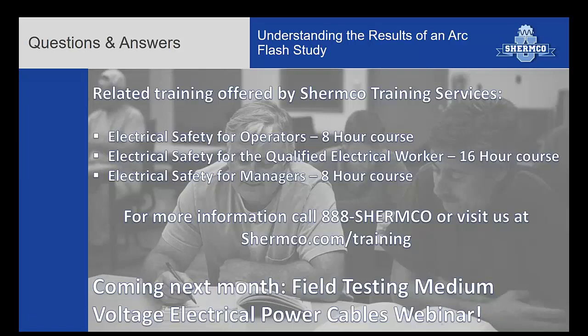You know, if you think of an arc welder, that's current, right? Not voltage. An arc welder almost has no voltage. So it's just this large amount of current on 480 volt systems that really creates this big hazard. And then also typically medium voltage has quicker trip times, not always, but typically. And one thing on the 480, between the transformer and the secondary, the protection's on the high side of the transformer and it's having to look through the transformer. That fuse was, for the past 20, 30 years, to protect the transformer. It wasn't to protect the low side. So now I think you'll see things change over time, but definitely the 480 volt seems to be where most of the high incident energy is.